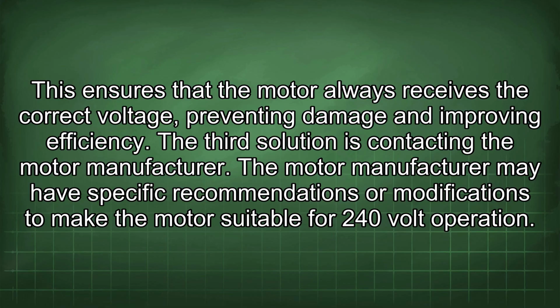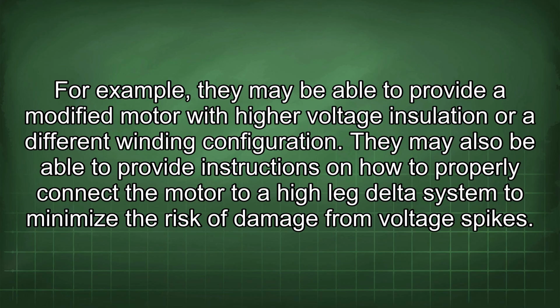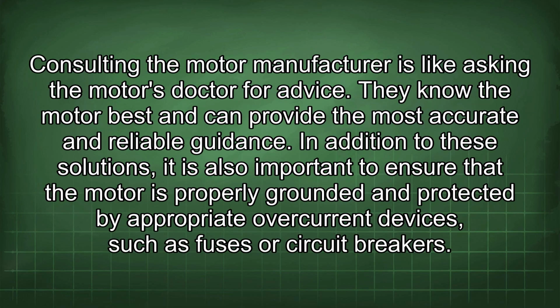The third solution is contacting the motor manufacturer. The motor manufacturer may have specific recommendations or modifications to make the motor suitable for 240-volt operation. For example, they may be able to provide a modified motor with higher voltage insulation or a different winding configuration. They may also be able to provide instructions on how to properly connect the motor to a high-leg delta system to minimize the risk of damage from voltage spikes. Consulting the motor manufacturer is like asking the motor's doctor for advice. They know the motor best and can provide the most accurate and reliable guidance.